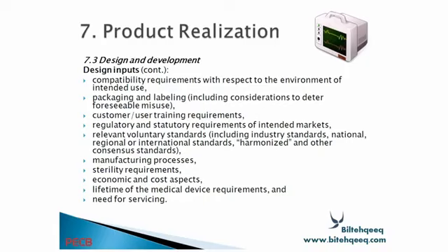Design input continuing: compatibility requirements with respect to the environment of intended use, packing and labeling, including consideration to deter foreseeable misuse, customer user training requirements, regulatory and statutory requirements of intended markets, relevant voluntary standards including industry standards, national, regional or international standards, harmonized and other consensus standards, manufacturing process, sterility requirements, economic and cost aspects, lifetime of the medical device requirements and need for servicing.